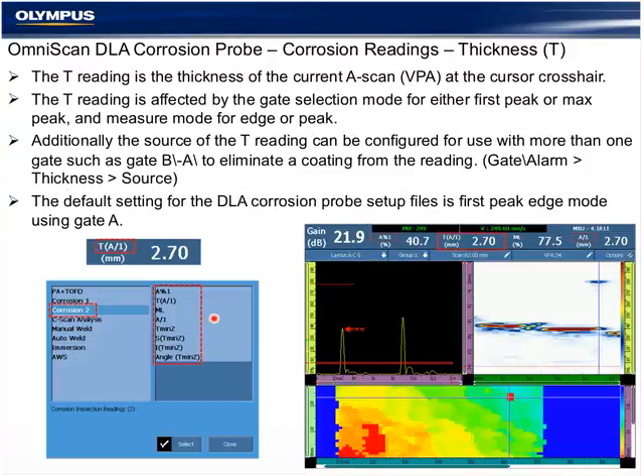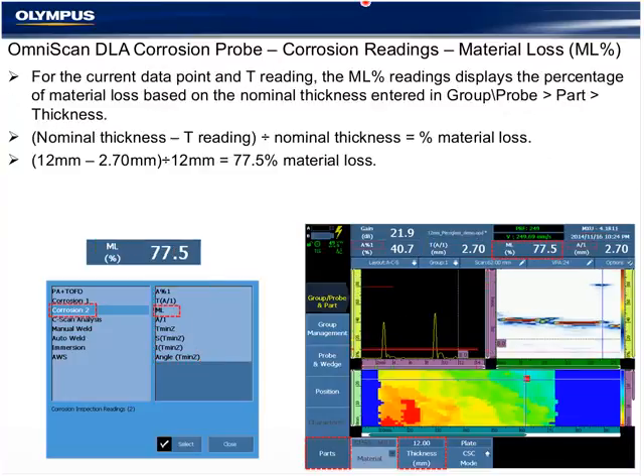So the three pre-configured files are also pre-configured using the Corrosion Group 2 of the default OmniScan readings database. This gives us 4 readings in 2 groups, 8 total readings, to include typically what's necessary for a corrosion inspection. On any single point, we'll see the T reading, the material loss, and the amplitude.